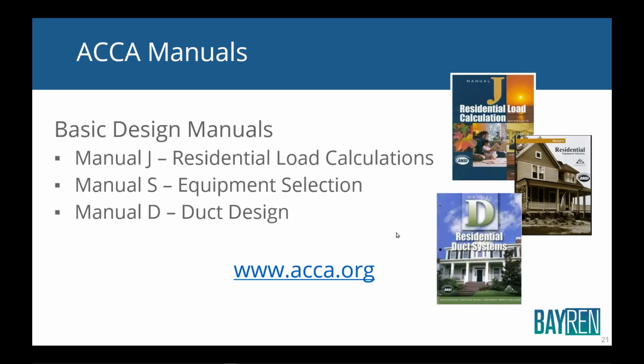The basic design manuals are JS&D. J is load calculations. S is equipment selection and determining the actual design capacity of an air conditioner and a heat pump. And then Manual D is duct design. How do you lay it out? How do you size the ducts? How do you make sure each room is getting the right airflow and things like that?